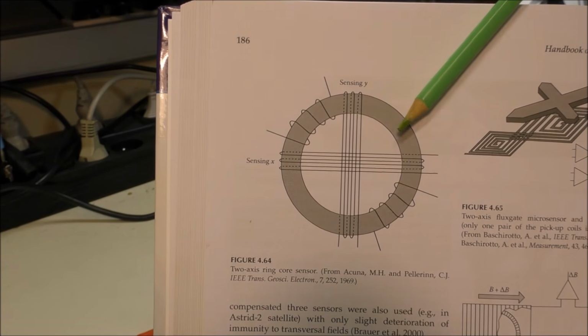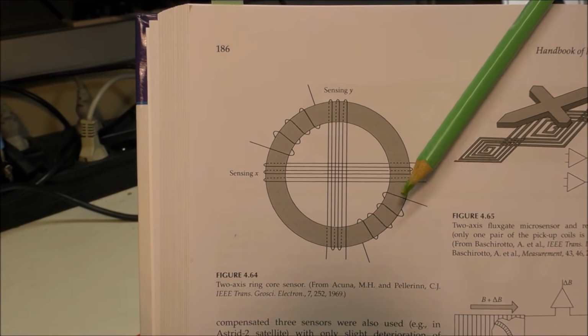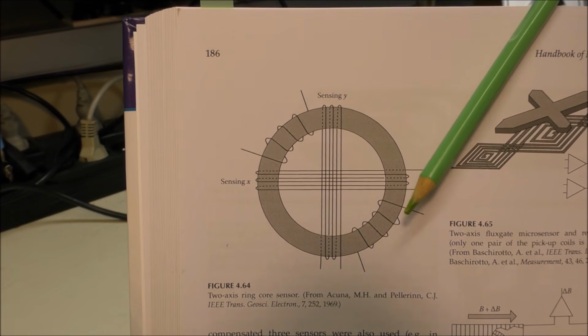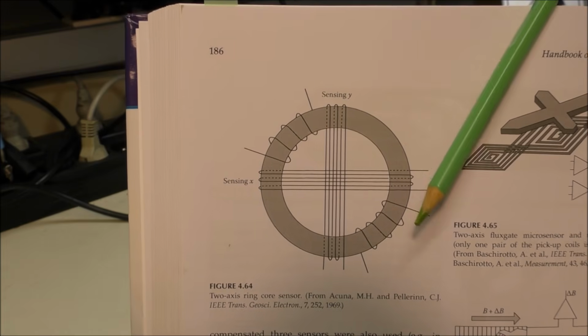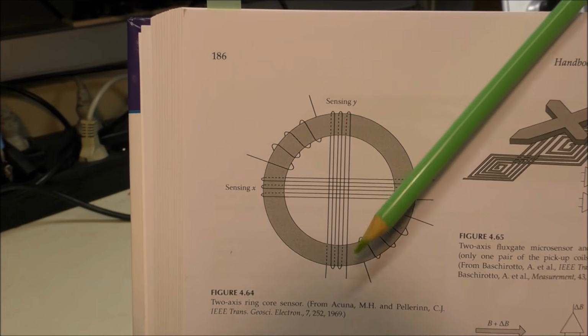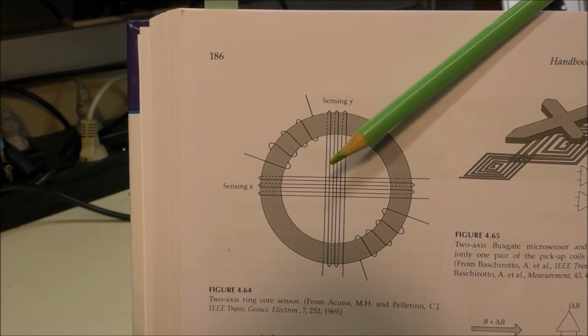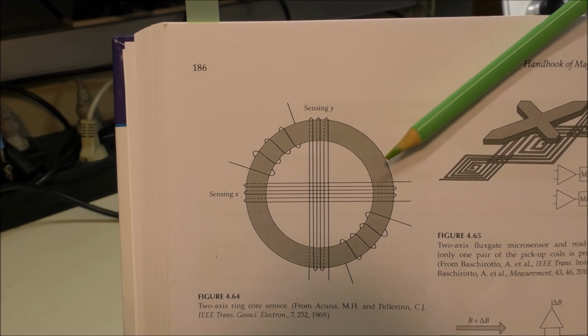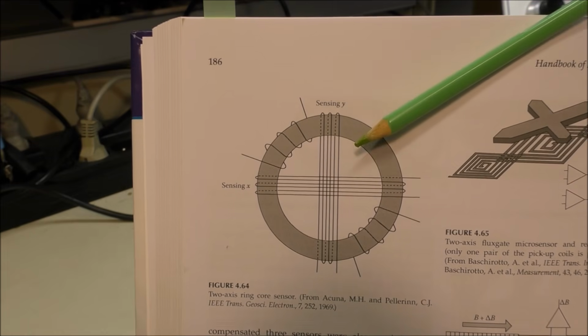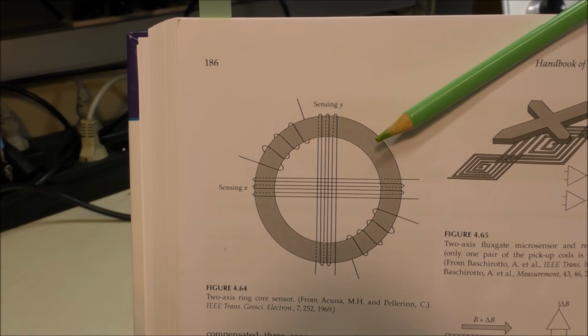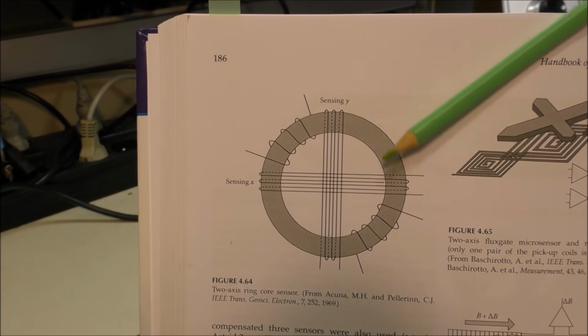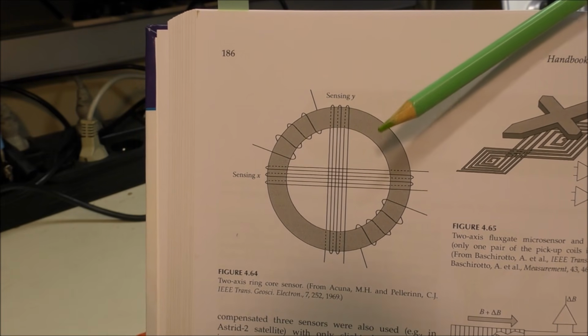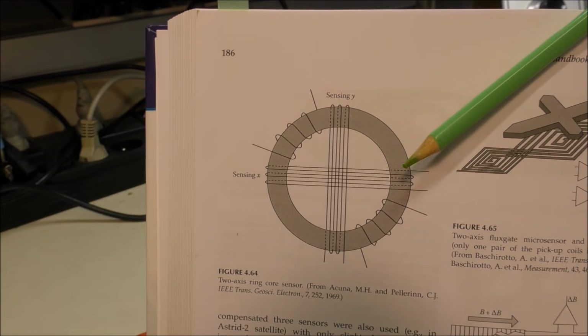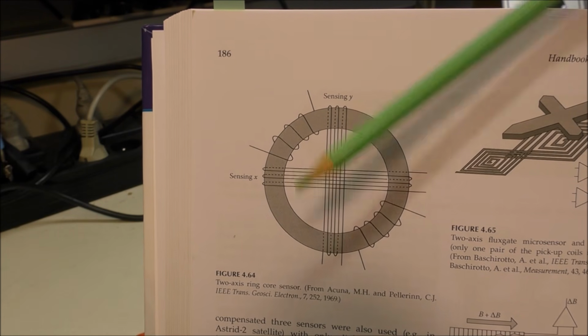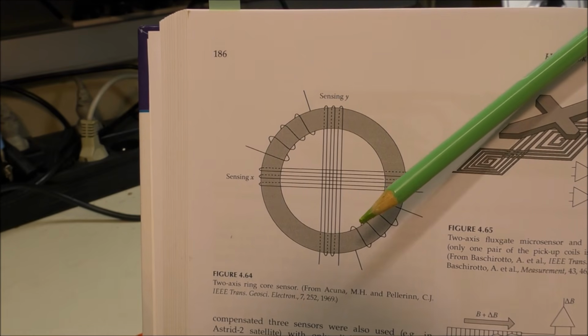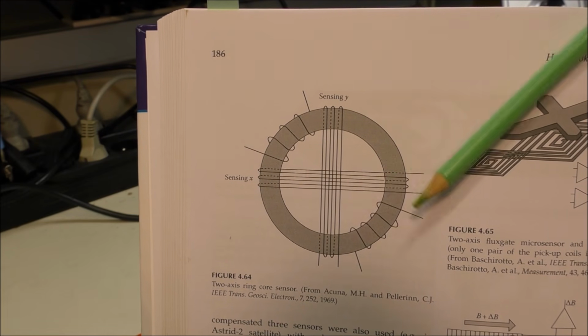Okay, it is something similar to that image here. This is a 2-axis ring core sensor, except that on that image we have only 2 excitation coils and we have 2 pickup coils. So the goal is to saturate the material. So the material is made with permalloy generally. So therefore there is a variation of flux around the core, because when the core is not saturated, the magnetic field is concentrated inside the core here. But when the core saturates, the core doesn't exist anymore, and therefore there is a magnetic field which is present all around the core. And the variation of flux is detected by these 2 coils here.